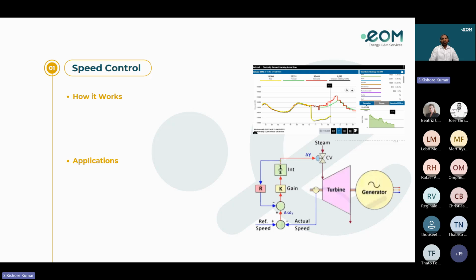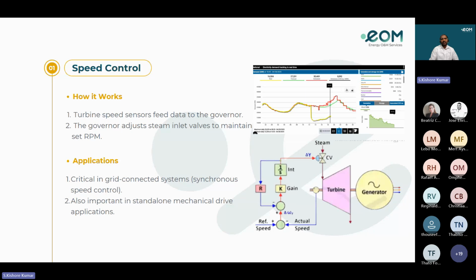The speed control. Our objective is to maintain constant turbine speed regardless of load changes. How does it work? Turbine speed sensors feed the data to the governor, which compares it with the reference speed, and based on the difference, the control valve will open and close. So the governor adjusts the steam inlet valves to maintain the set RPM. Here we can see the control loop, how it is operating, and the applications. It is critical in grid-connected systems and synchronous speed control, and also important in standalone mechanical drive applications. And here we can see the graph that shows the recent grid failure in Spain.